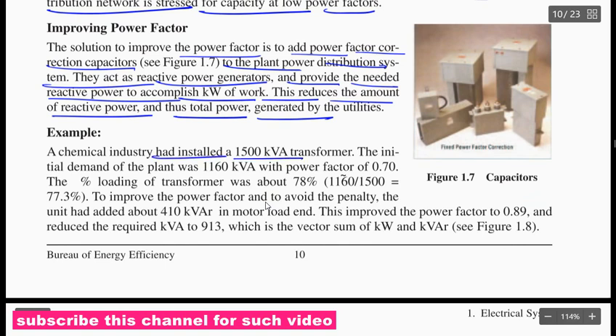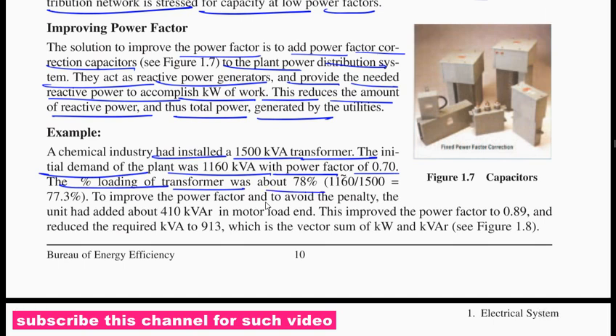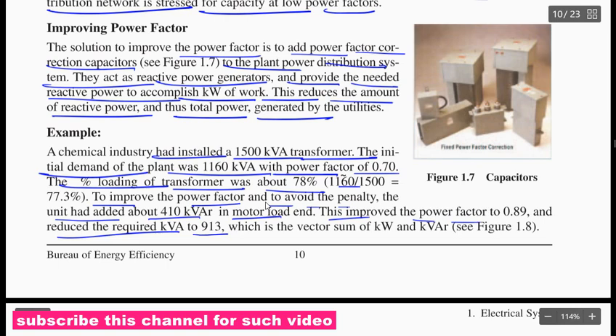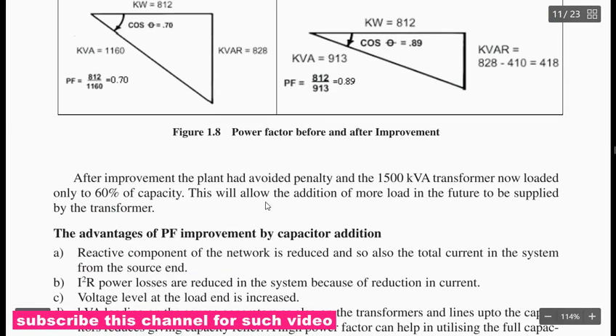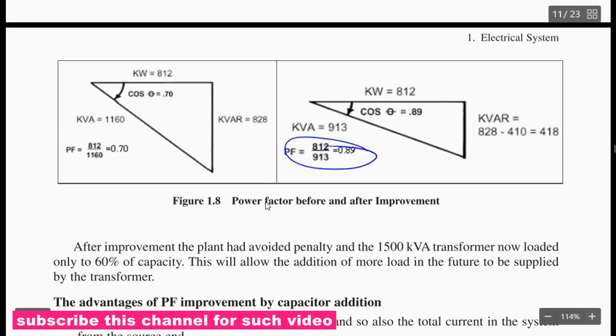The chemical industry has installed a 1500 kVA transformer. The initial demand of the plant is 1160 kVA at a power factor of 0.7, with loading of the transformer at about 77%, that is 1160 divided by 1500, that is 77.3%. To improve the power factor or to avoid the penalty, the unit added 400 kVAr to the motor load, and this improved the power factor to 0.89 and reduced the required kVA to 913, which is the vector sum of the kilowatt and kVAr. So that is 0.89, kilowatt divided by kVA. Kilowatt divided by kVA, that is 0.7. This is the power factor before improvement.